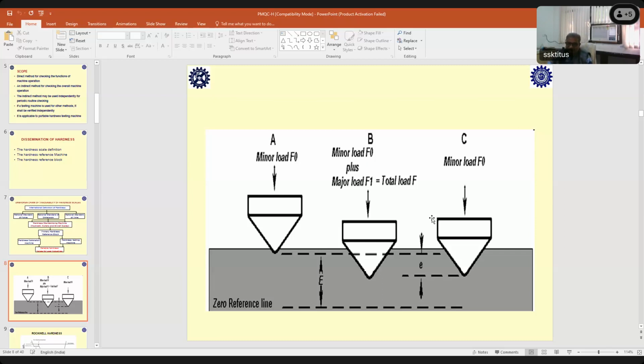You don't have to really worry about the numbers at this stage, because what you have to see is, first of all, you apply a preliminary force. Let me not give you any number. You apply some preliminary force, then you wait, then you apply the total test force, that is the additional test force. Then you remove the additional test force. Then you have to measure how much permanent damage or permanent indentation depth this conical indenter has made on that sample. That permanent indentation you have to measure.